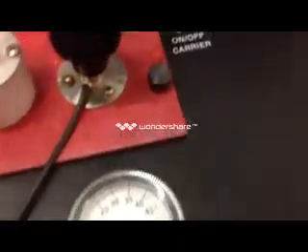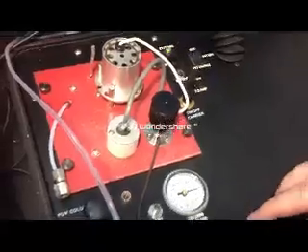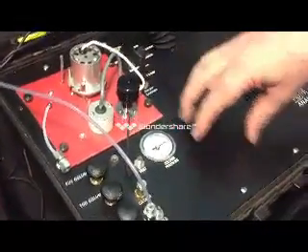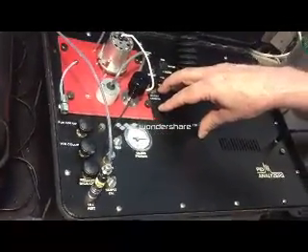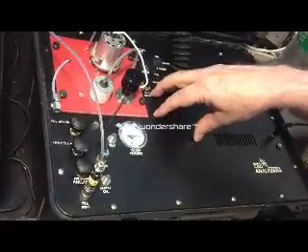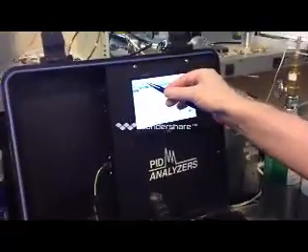The top of this comes off, so you can get at the column and get at the detectors. There's actually a cylinder inside here that contains about 30 liters of carrier gas at about 2,500 psi when it's full, and there's a pressure indicator on the instrument that basically tells what the pressure is. There's a low pressure indicator, but you can also run this off carrier gas like we're doing right now.